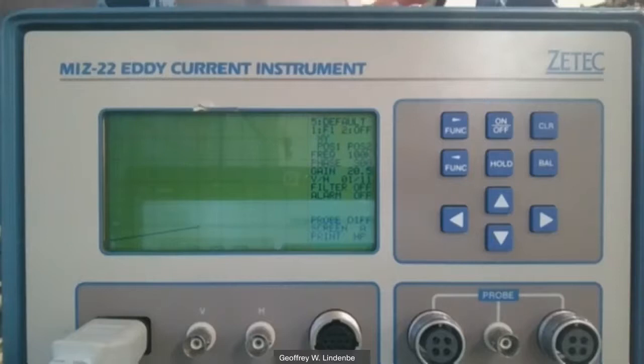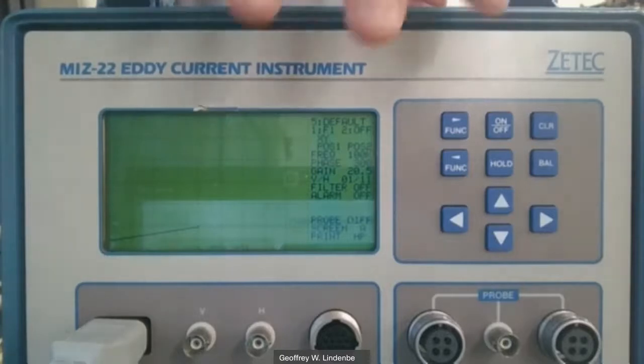And then that magnetic field, when you put it near a part, is going to go into the part, and it's going to induce the little eddy currents in the part. And then those eddy currents are going to have their own magnetic field that then pushes back against either the absolute coil or one of the reflection or differential coils. And then that signal gets fed back to an amplifier, which then drives the display.